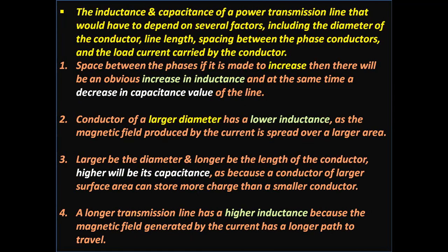The inductance and capacitance of a power transmission line depend on several factors, including the diameter of the conductor, line length, spacing between the phase conductors, and the load current carried by the conductor. Number one, if the space between the phases is increased, there will be an obvious increase in inductance, and at the same time a decrease in the capacitance value of the line.